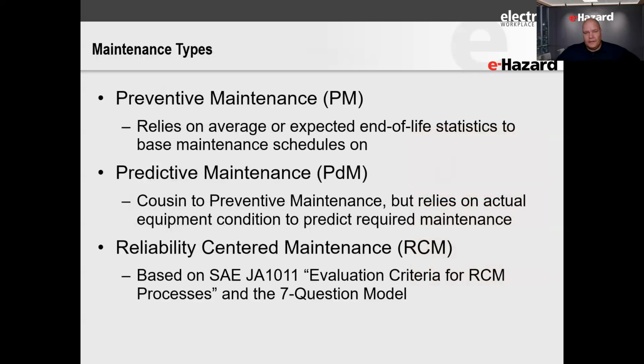When we look at the tables specifically in 70B, we see some equipment or procedures fall under preventive maintenance, where it's just changing your oil regularly—routine, calendar-based maintenance to keep the equipment up and running. Some tests fall under what we call predictive maintenance, where we're taking an IR scan so we can see hot spots and try to identify when things are going to become an issue and get ahead of them.